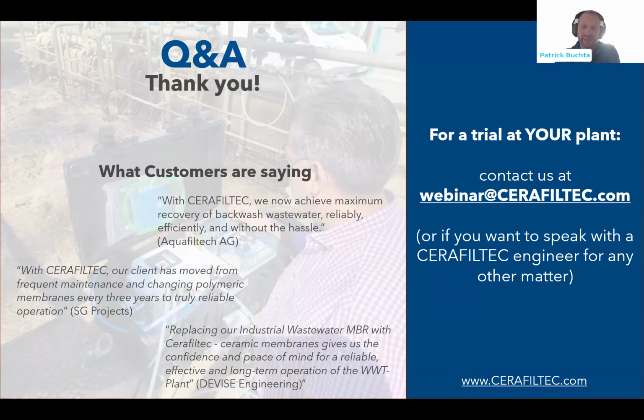So for me, it doesn't make sense to have a 100% barrier for particles if you consider 1% fiber breakage per module of the capillaries. That doesn't make sense to me. I think we can also build on nsf.org. You see the log removal details of all the polymeric membranes for the American standards, and the CERAFILTEC solution actually has a higher LRV removal in the NSF 419 tests than 0.02 micron polymeric membranes. That's a fact, publicly available, that we can lean on.